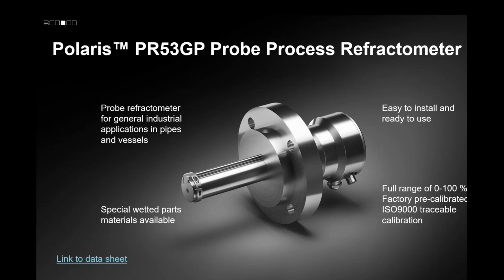You may have steam running throughout your facility or hot water. You simply connect your steam or water to this and control it, though you may have to use some high pressure valves and so on. This is where the transmitter comes into play. You use it to control the duration and frequency of cleaning, and it actually cleans the sensor tip before you have a problem, maybe every 10 minutes, preventing any buildup of potential coating.